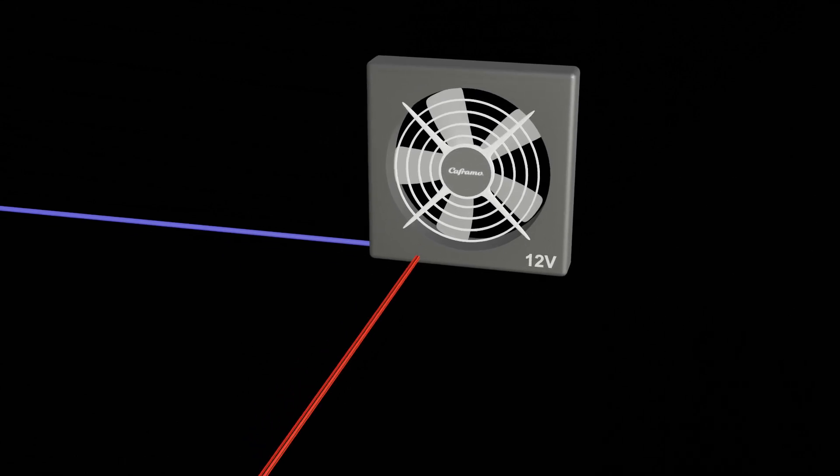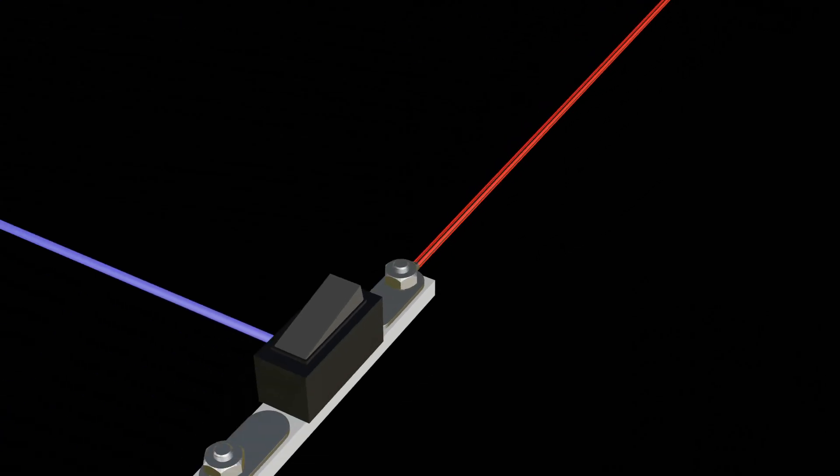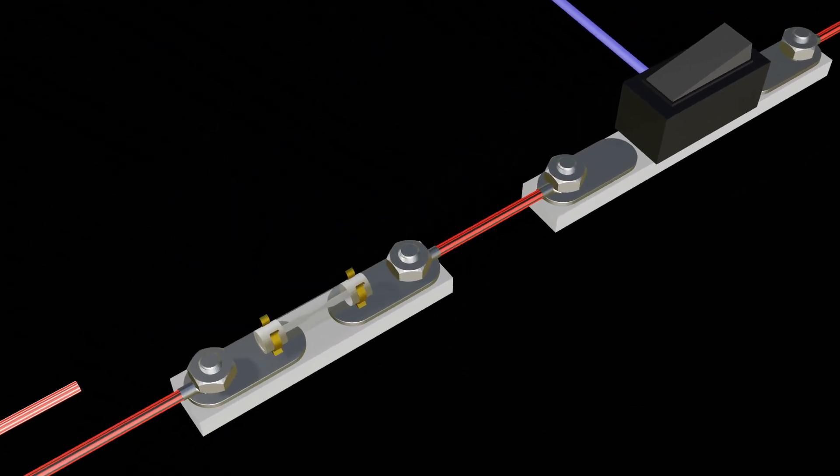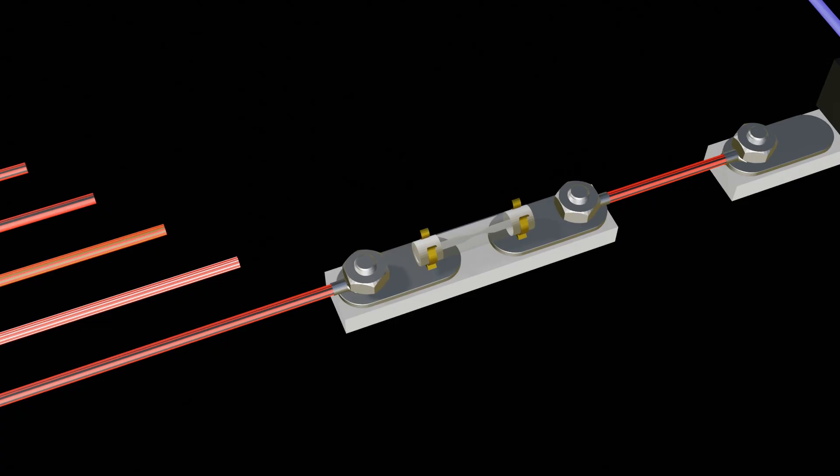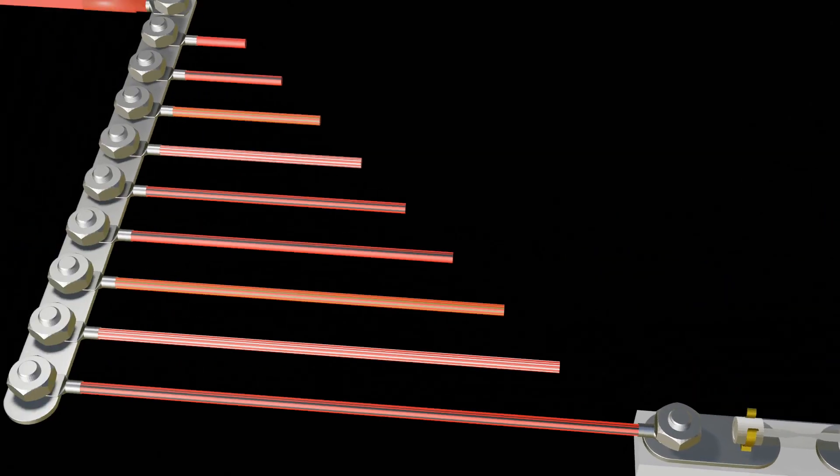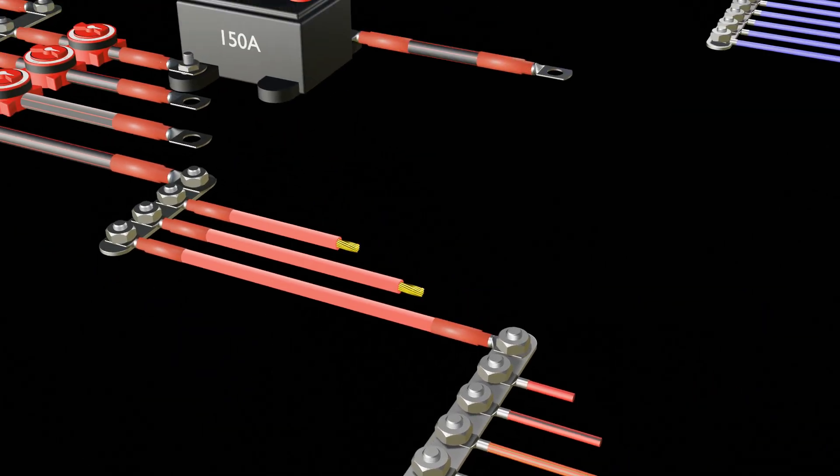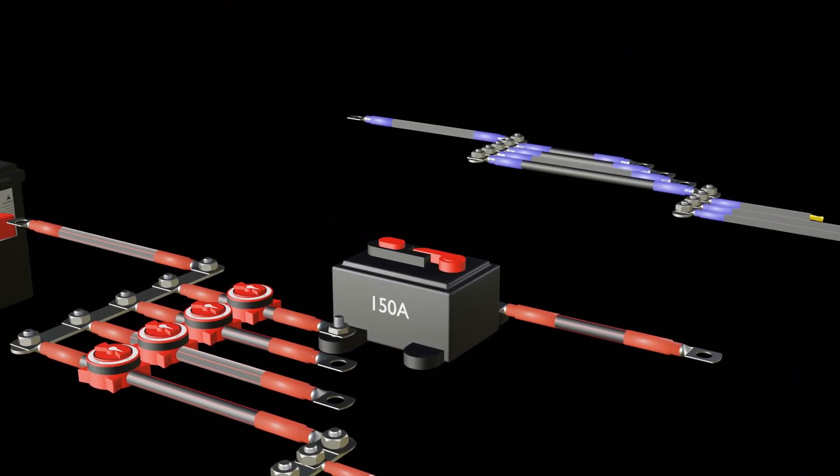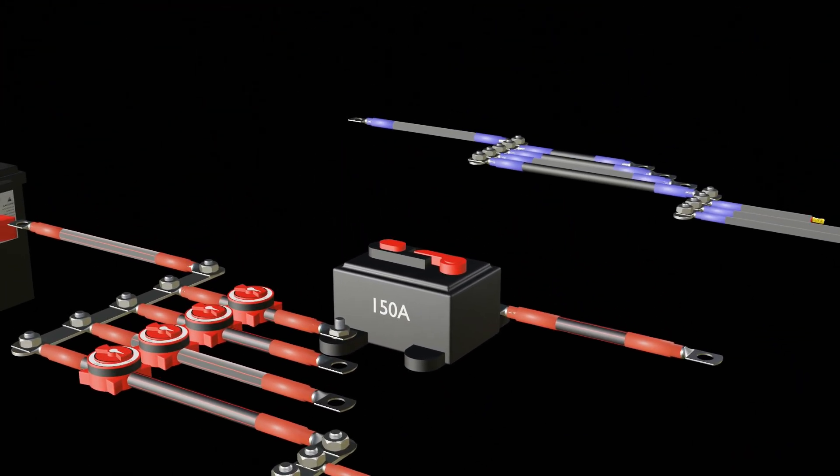If we go and check the switch and it has no power, then we take a step back and check the fuse. If the fuse is gone, try to work out why, correct the problem and replace the fuse. If the fuse is good, go further back and check any circuit breakers and test for current using the multimeter at the different connections.